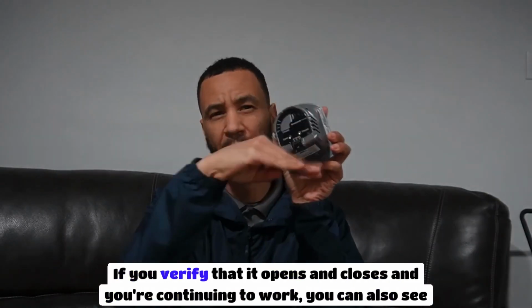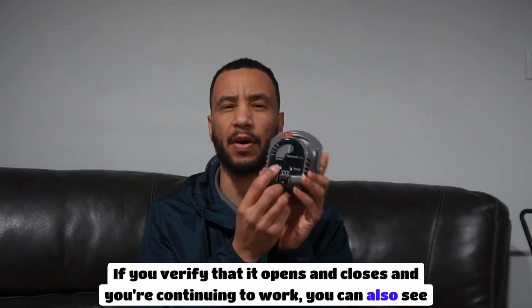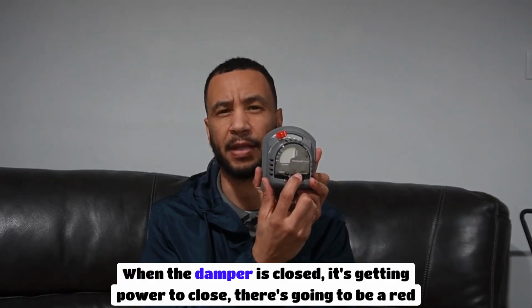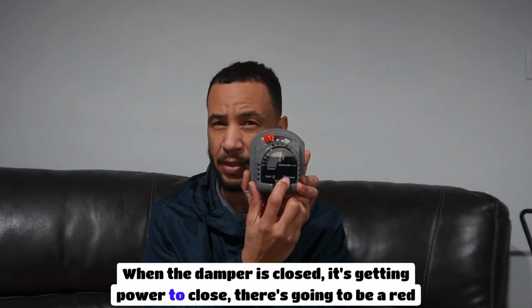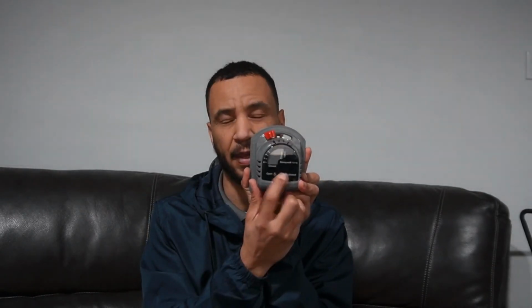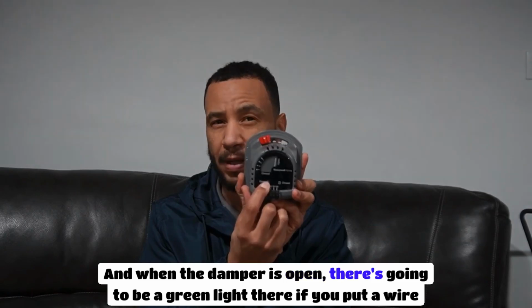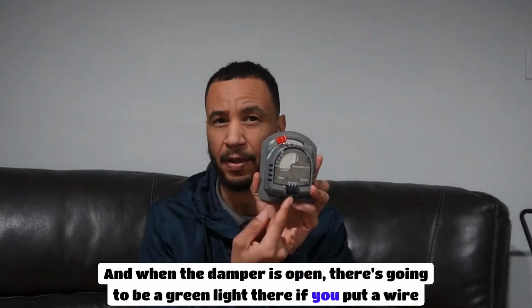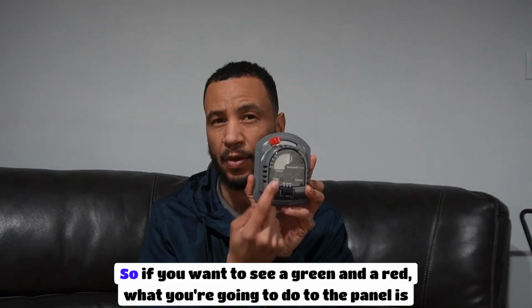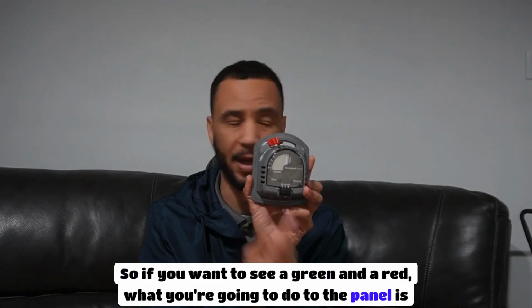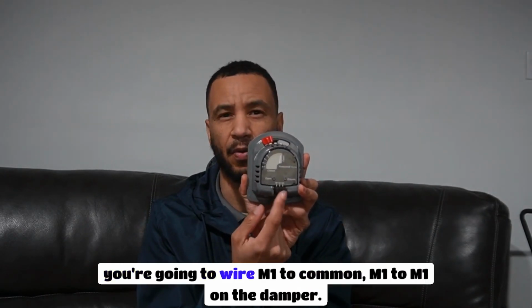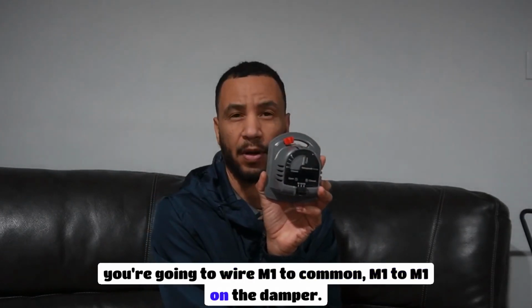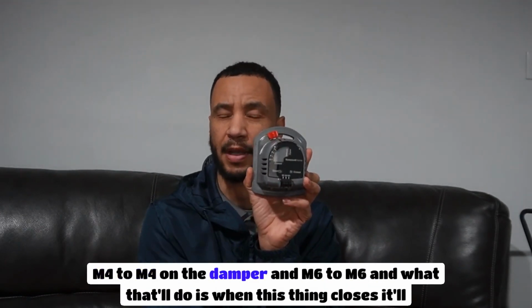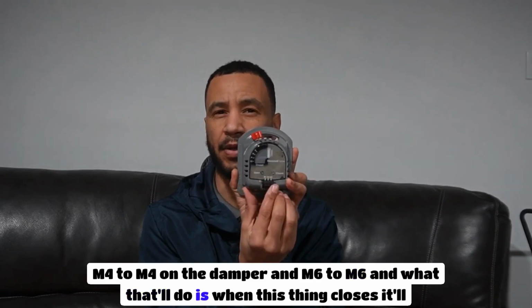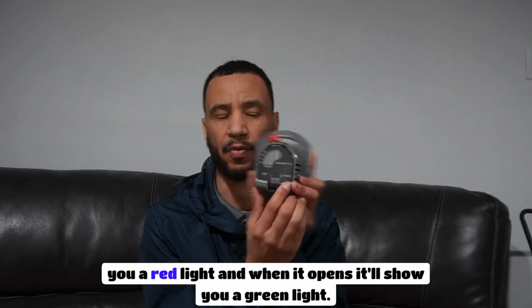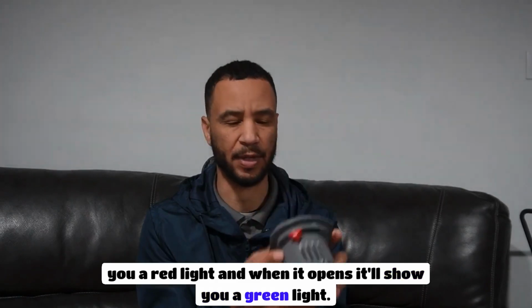If you verify that it opens and closes and you're continuing to work, you can also see the red light. When the damper is closed, it's getting power to close, there's going to be a red light there. And when the damper is open, there's going to be a green light there if you put a wire on M4. So if you want to see a green and a red, what you're going to do to the panel is you're going to wire M1 to common, M1 to M1 on the damper, M4 to M4 on the damper, and M6 to M6. And what that'll do is when this thing closes, it'll show you a red light. And when it opens, it'll show you a green light.